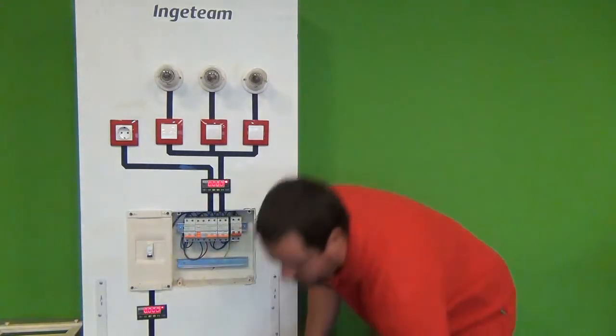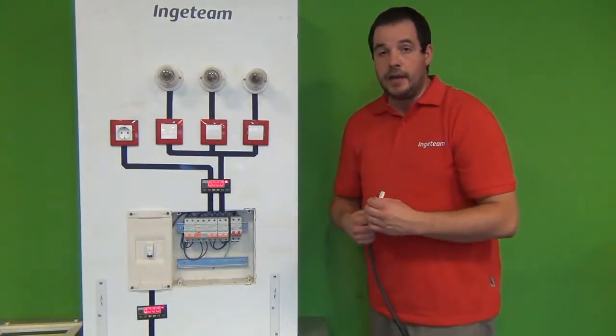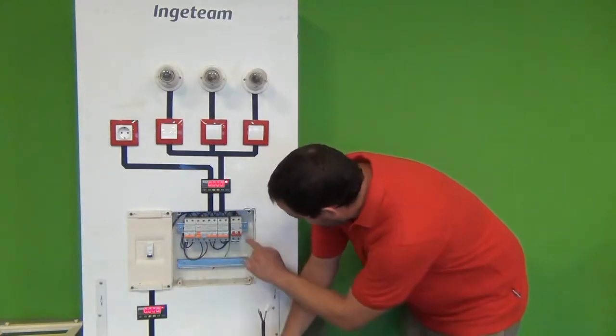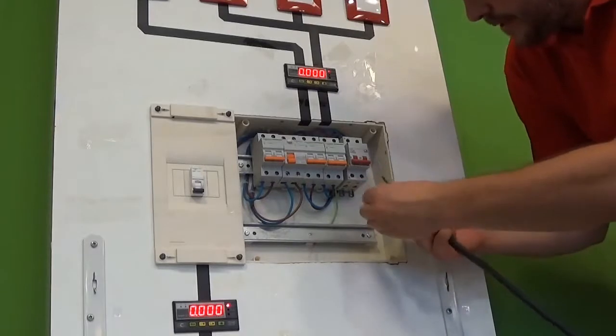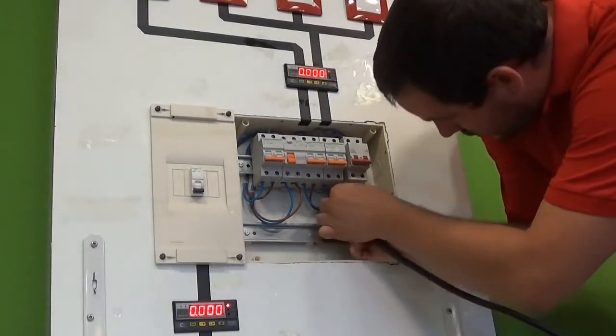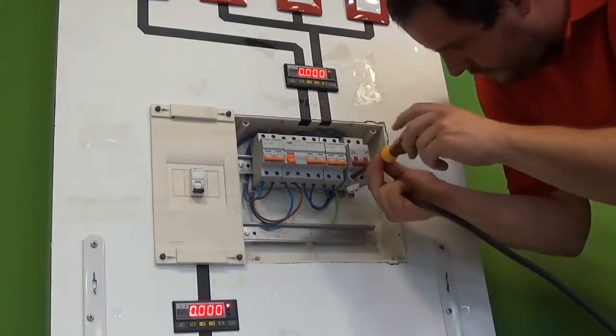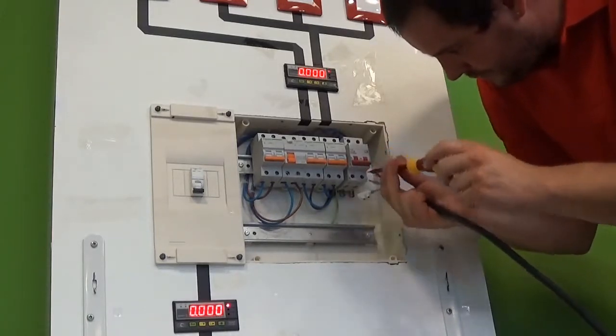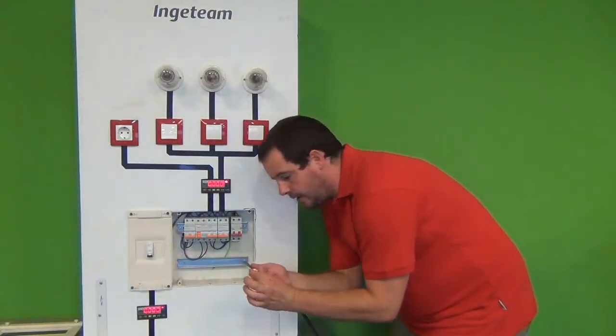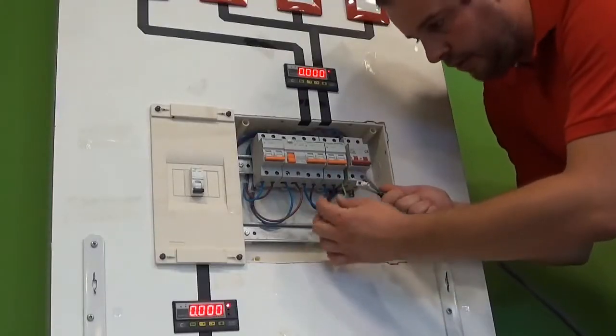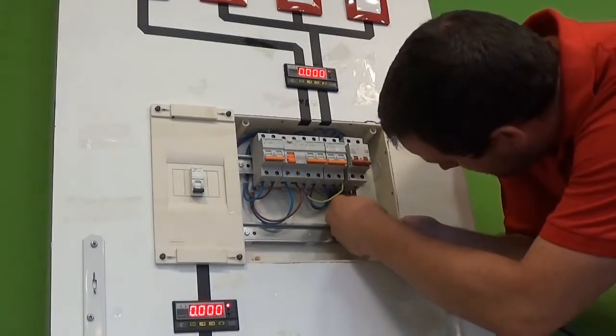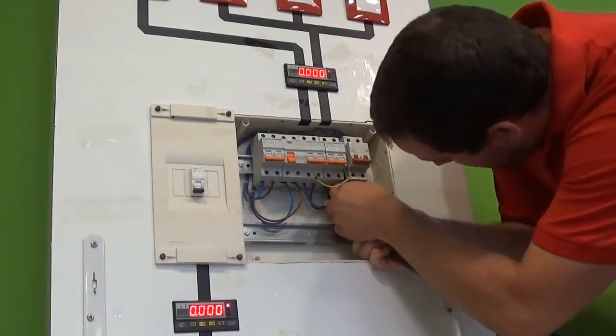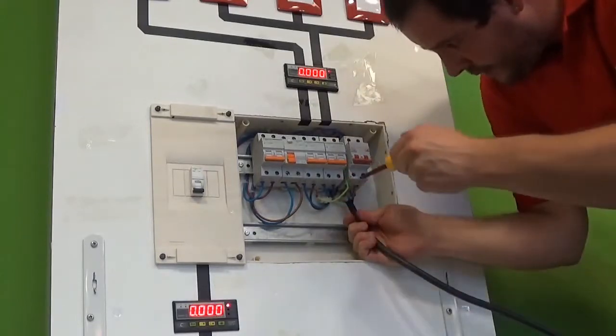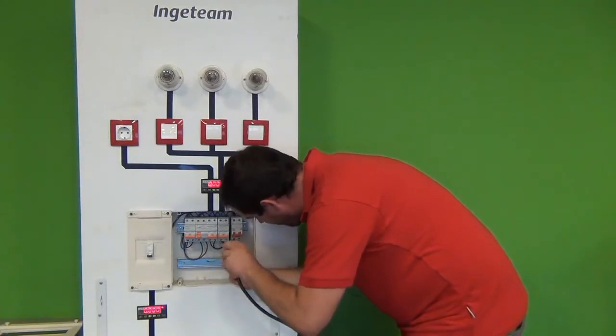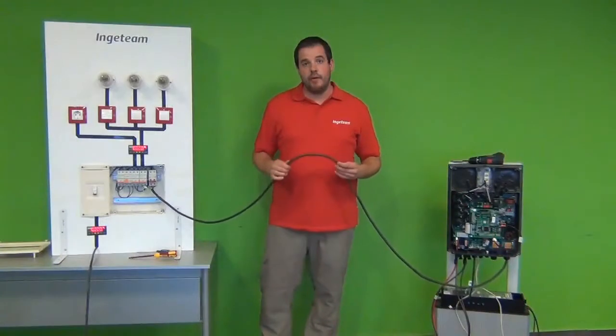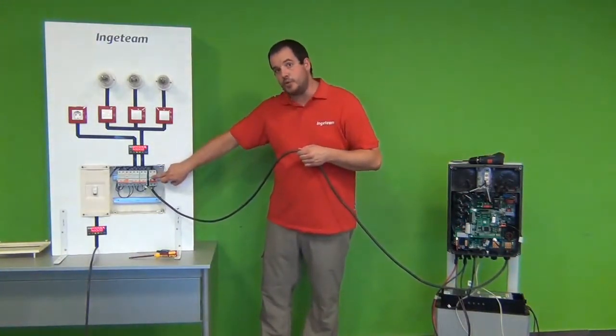And now it is time to take these cables and then connect them in the right position. Here we have line, neutral and ground again, okay? So in this thermal magnetic breaker, the way to wire it is like this, okay? Neutral and line goes to the thermal magnetic breaker. I'm going to open the screws a little bit more. And there's also another connector for ground that needs to be connected to the ground of my property. I have left a cable here to do so. So now I'm going to proceed to, as I said, connect those cables. There we go. So now the AC side of the inverter is connected to my main switchboard.